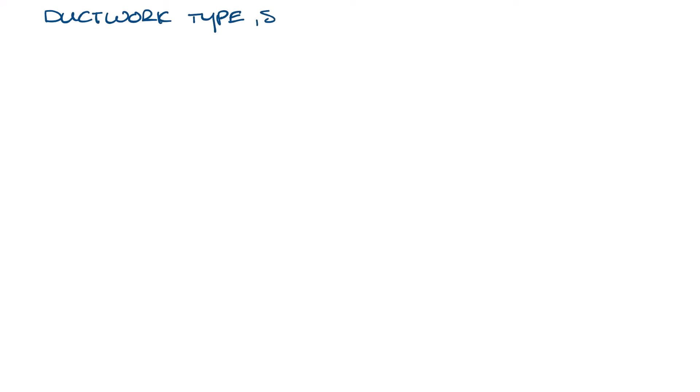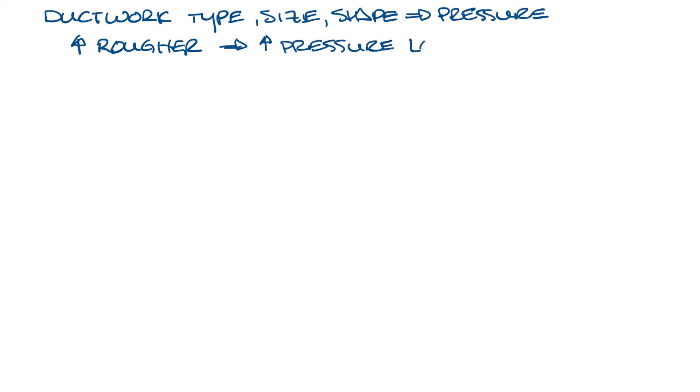The type of ductwork, size, and shape all affect pressure differently. For instance, the rougher the ductwork is, the more friction loss it'll have, so unlined ductwork will be less rough and therefore have lower friction losses than fiberglass lined ductwork or flex duct.